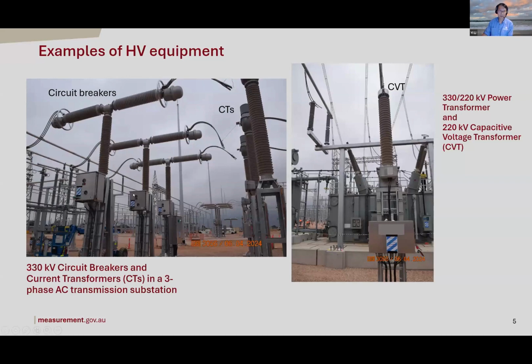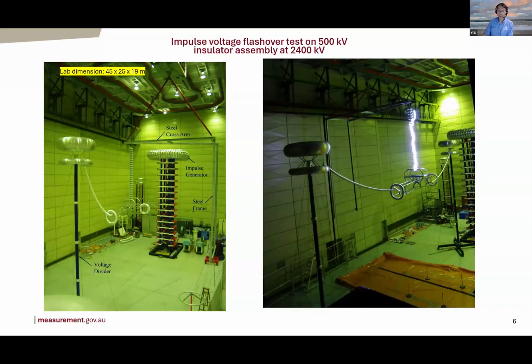Some other examples: you have circuit breakers. They're not like a wall switch, they are big. You have current transformers for measuring up to a few thousand amps of current. You have transformers for measuring the voltage. This particular one is called a capacitive voltage transformer. Of course, you have magnetic voltage transformers as well. All of these need to have their insulation tested to ensure they work properly and safely. They not only work at the network voltage, like 330 kV, they also see lightning strikes. They also see switching pulses generated by circuit breakers or other types of switching devices. So there are quite a few other voltages used in testing, not only AC or DC voltages. So where is the testing done?